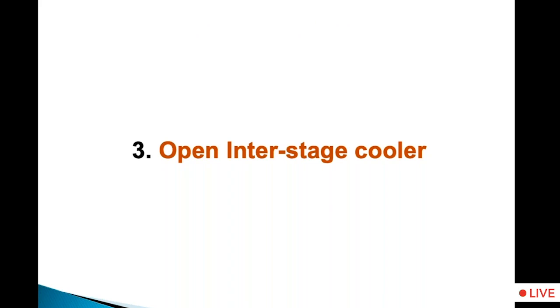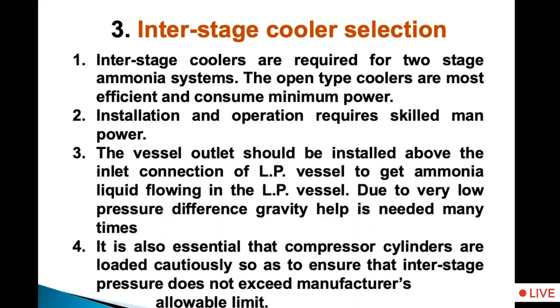The next important vessel we come to is the interstage cooler. These interstage coolers are used only in two-stage refrigeration plants, not in single-stage refrigeration plants, because the low pressure gas from the discharge of the low stage goes into the interstage cooler, and then it is cooled down, the superheat is removed, and then the gas is compressed in the high stage. There are two types of interstage coolers. The open type interstage cooler is the most efficient interstage cooler.